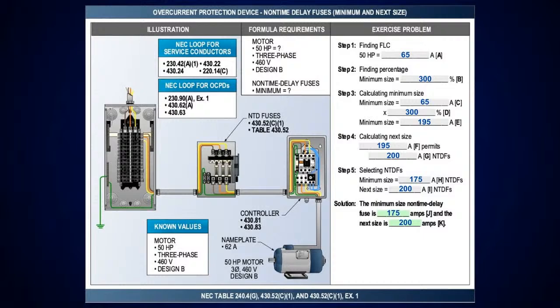All right. Now, the first one, everybody remember this. I'm going to go over this a little bit just to refresh everybody. Anytime you're sizing your overcurrent protection devices or conductors, you want to use the amperage values that are in the tables in 430.247 through 250, and we get that permission over in 430.6(A)(1). When I'm doing the overload protection, I'm going to look at 430.6(A)(2), and it's going to tell me to use the nameplate. I just want to make sure everybody remembers that.